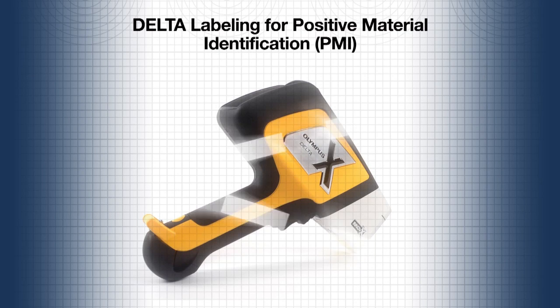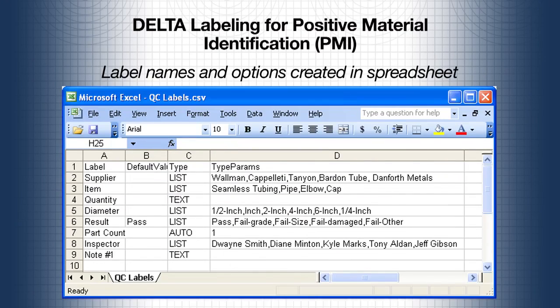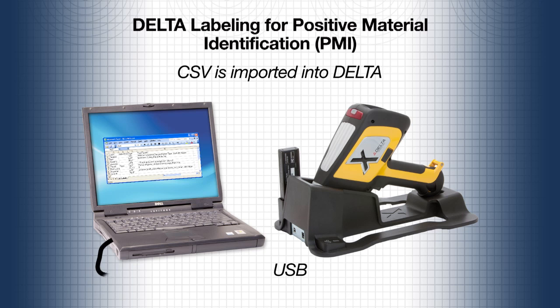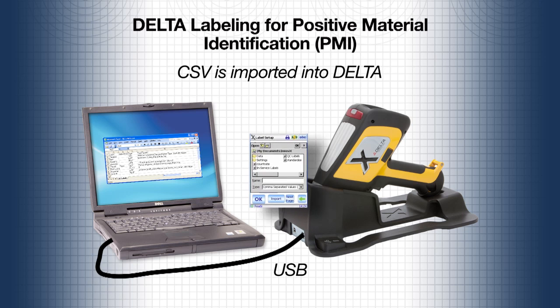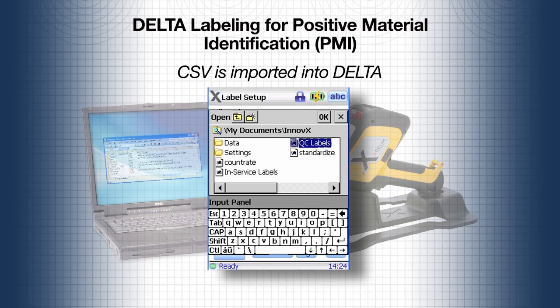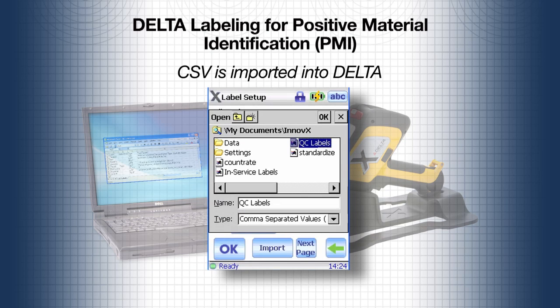Creating and populating labels on the Delta is a simple process. First, the label names and their options are created in a spreadsheet. Then the CSV version of the spreadsheet is imported into the Delta, which automatically creates the labels and their options. This is a great way to reduce your analyzer's setup time.